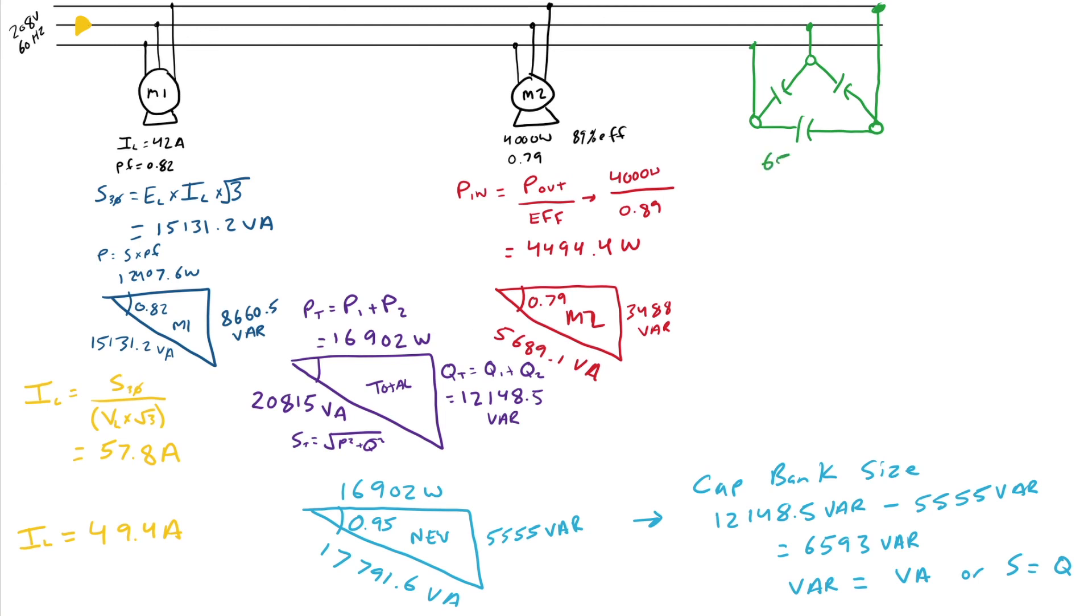So I'm going to come up here, write that down, 6,593 VAR. Okay, using the same formula as before, I can determine that I need my line current here, my line current, I line to the capacitor to be 18.3 amps.